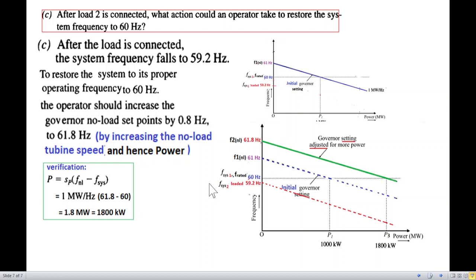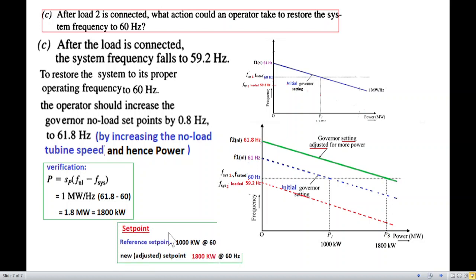To verify: using the formula with the new no-load frequency set point, the power available is 1800 kilowatts. Setting the set point to 61.8 Hz and applying the slope of 1 MW/Hz with 1800 kW load gives: f_sys = 61.8 − 1.8 = 60 Hz. This confirms the system frequency is restored to 60 Hz.